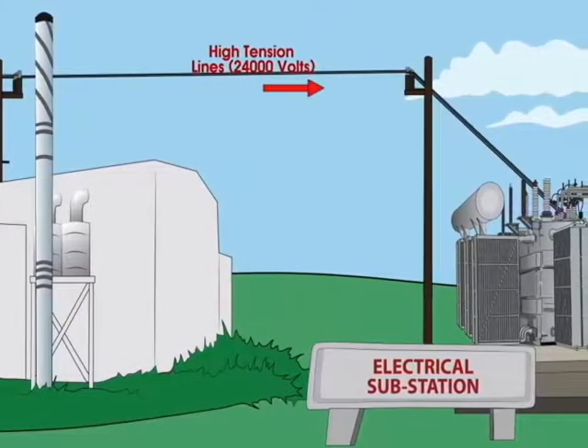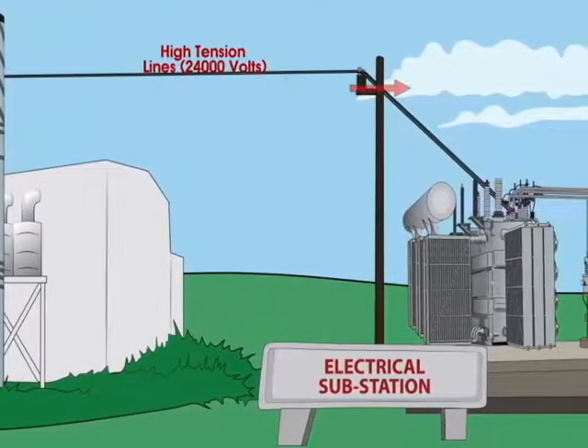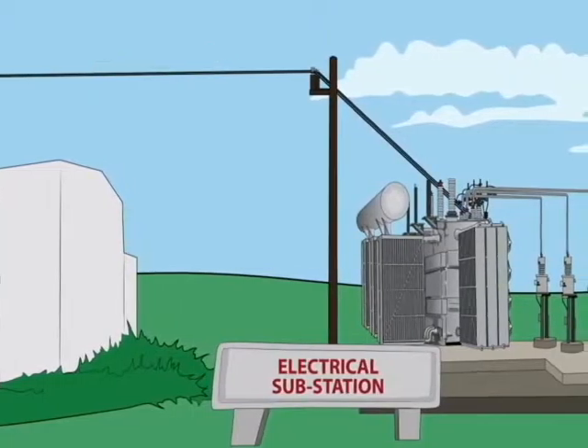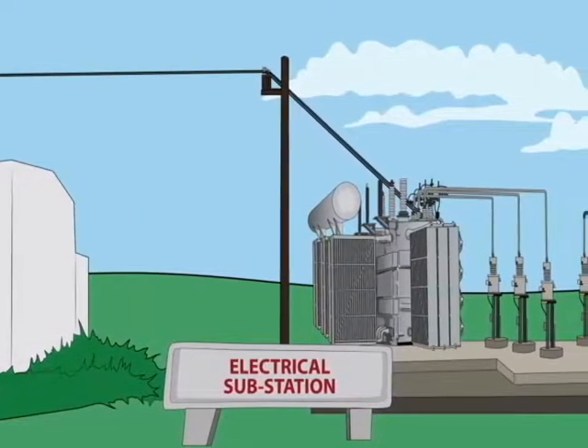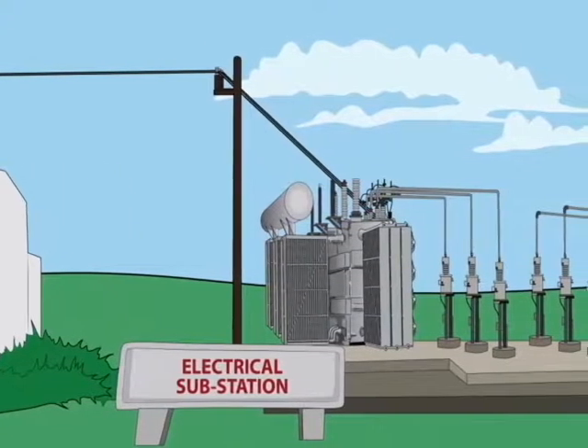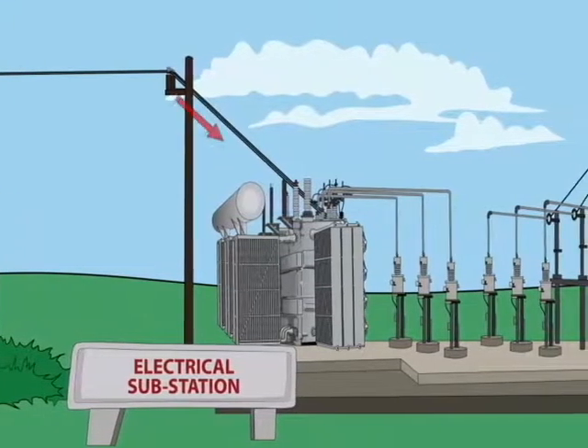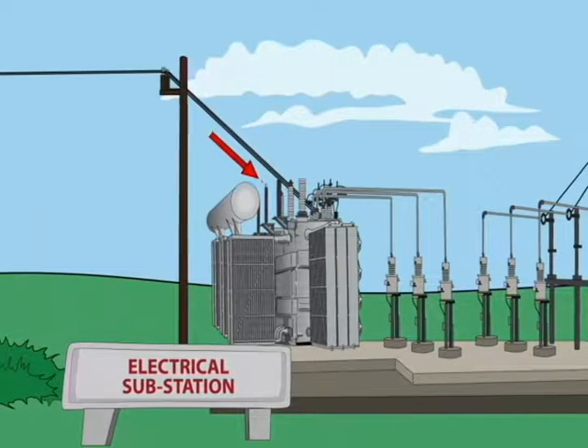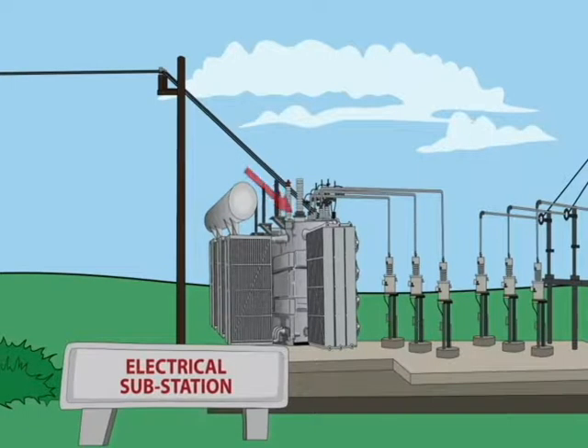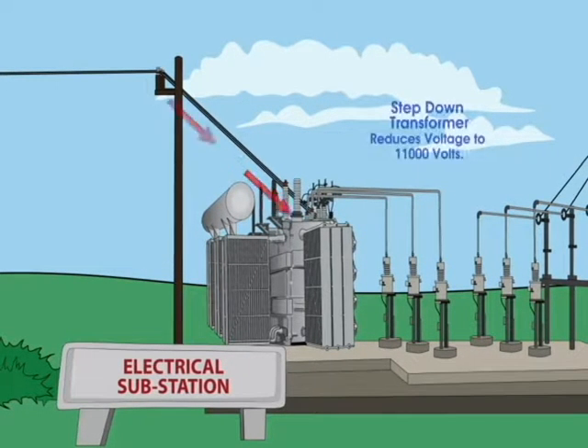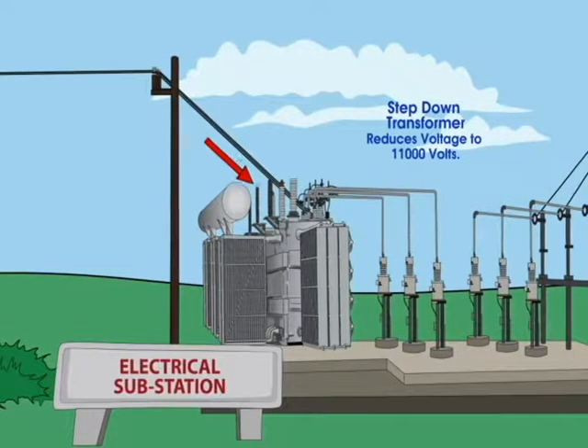So we transmit from the generation station at Spring Garden to a number of substations across the island. There are approximately 16 substations across the island which serve the different villages and communities over Barbados. Once the 24,000 volts reaches the substation, we now step it down to 11,000 volts.